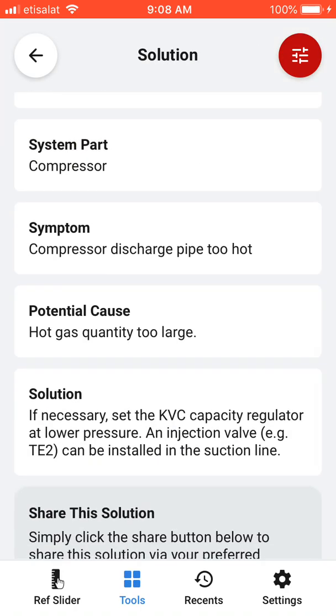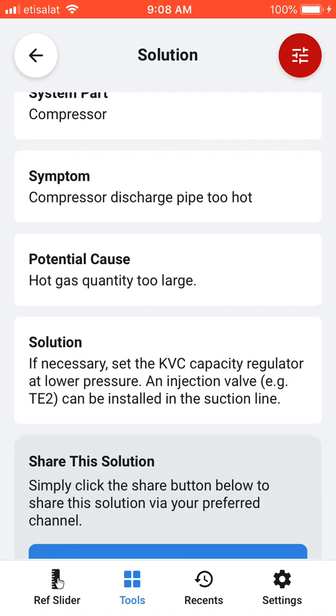In this case, the solution is to set the KVC capacity regulator at a lower pressure, and an injection valve can be installed in the suction line.